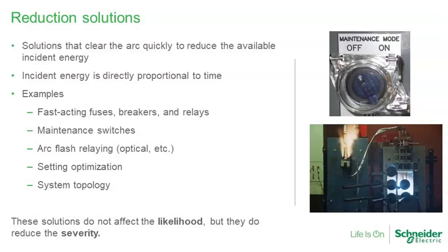The third thing I've got there, what I call arc flash relaying. We've seen this developed in the last, particularly over the last decade or so, more and more systems that really are kind of dedicated towards arc flash detection. One of the big categories of that type of solution are optical systems, fiber optic or point sensors that actually look for the light that's created by an arc flash event. You can see in the picture on the bottom right there, some pretty bright light that's associated with that arc flash and that equipment. And so if we can detect that, there are those relays out there available that can clear or can operate very quickly, as little as 2 milliseconds or less when an arc flash event is detected, compared to typical detection times that are at least 10 times longer than that, and that's for things that are operating very quickly. So it can be a very powerful solution method in order to help reduce those arc flash energy levels.